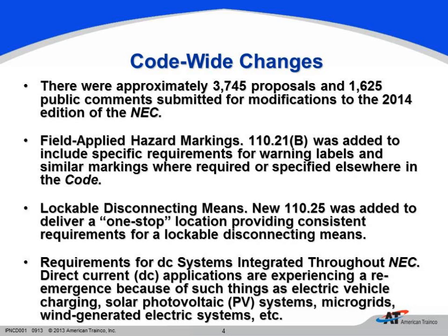Continuing and staying with photovoltaics, because there were some major changes in this article. In 690.12, they have a requirement now that we have to be able to shut down these photovoltaic systems within 10 seconds. And the biggest reason for this is because fire personnel might come to a building. There are two power sources, the utility and the photovoltaic system. And the photovoltaic system, in the past, is always going to be energized. So now they've given us this requirement that for all the conductors that are associated with that photovoltaic system, if they are 5 feet in length inside a building or more than 5 feet, then those are going to have to be able to be shut down within 10 seconds.